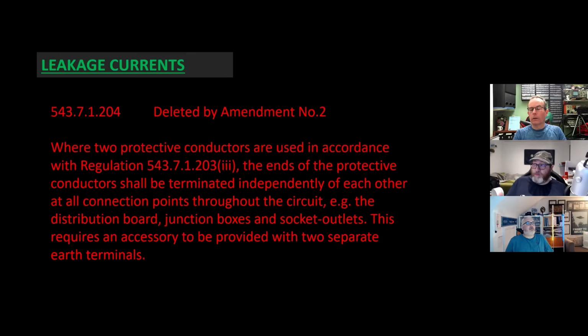That's not a problem now because we have to have RCDs. And if we have to have RCDs to 30 milliamp, we know with selectivity that we're not allowed more than 9 milliamp on that circuit. So because we have to have no more than 9 milliamp on that circuit, it doesn't require as much harsh protective conductor current regulation because we're not allowed to go over 9 milliamp. So that's why this has been changed.